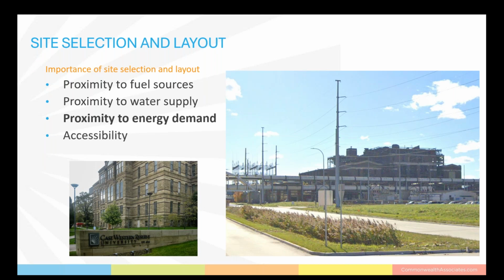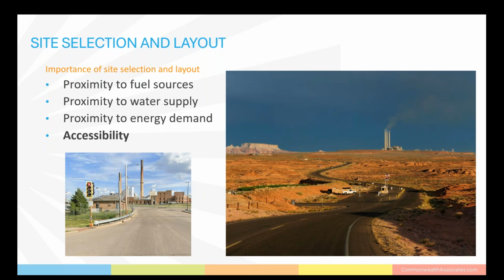So from a general arrangement standpoint, the interconnections to those facilities may require trestles, additional roadways, underground duct banks, or overhead power lines. Last is accessibility for general maintenance and operation. Roadways could also be used for the construction of the plant. So this means that there needs to be some consideration for the overall roadway capacity.